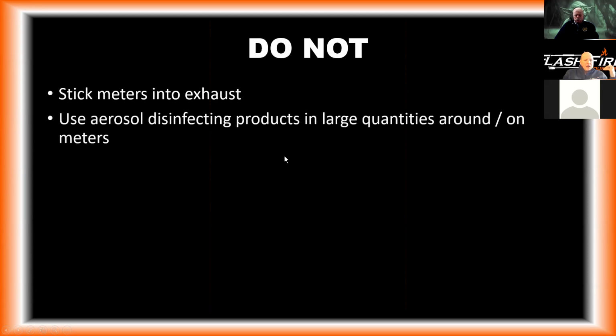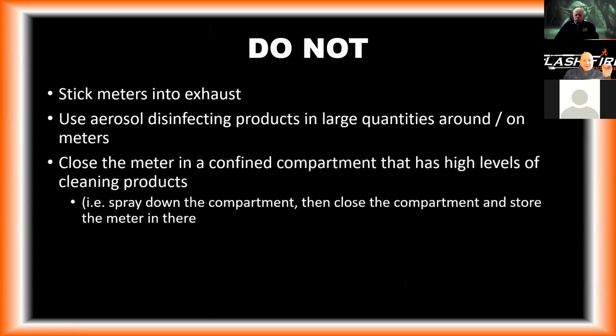I mentioned that. If you guys are still doing aerosol cleanings, just be very careful. Really don't want to spray it directly on the sensors. They have a lot of chemicals in there that could potentially be cross-sensitive or poison the meters. So pull the meters out of the compartment if you're going to spray it down. Don't spray the compartment down, then put the meter in there and close the compartment. Make sure you let it air out.